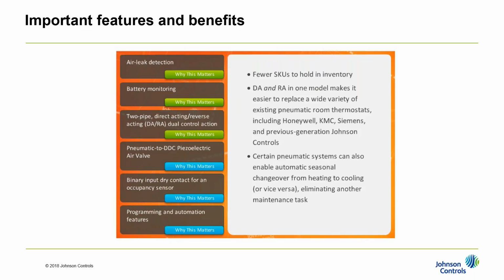With our pneumatic thermostats, one thing we experience is we get a call for replacement, ship out a direct acting thermostat, only to get a call a few days later where the customer actually needed a reverse acting thermostat. This particular device, one SKU, will do either. It's a software selectable switch. If you guess wrong, you just switch it the other way to get it right. We as the manufacturer don't have to stock multiple SKUs, and you as the customer don't have to worry about returning the one you accidentally bought and buying the other one.